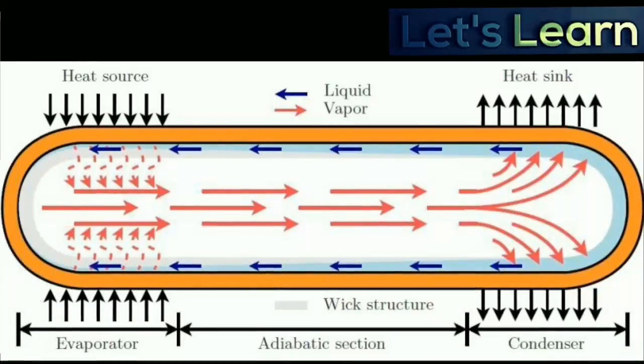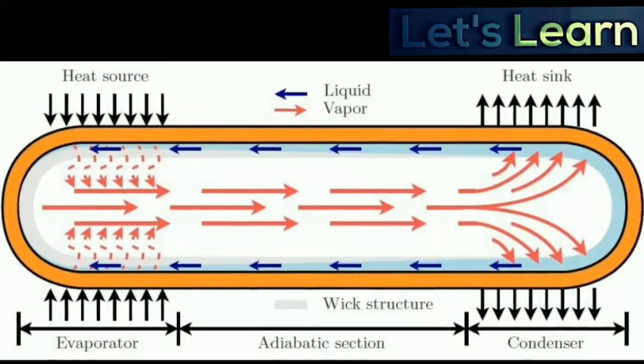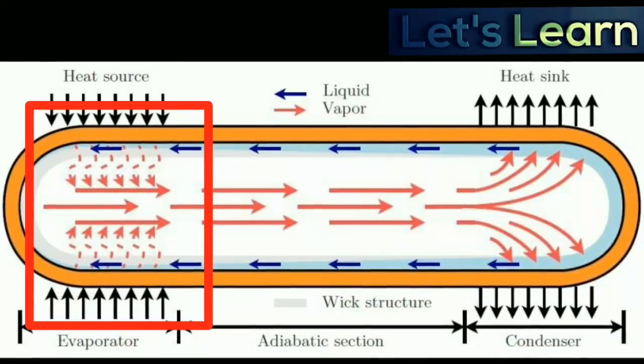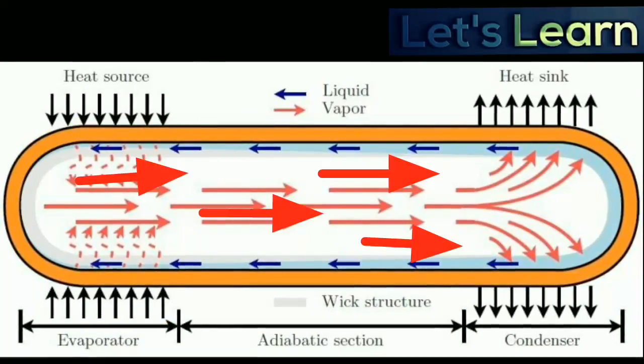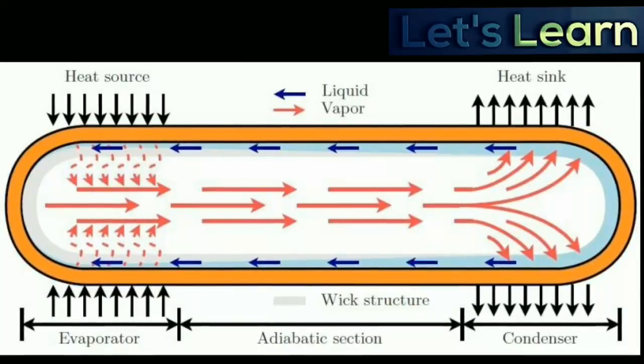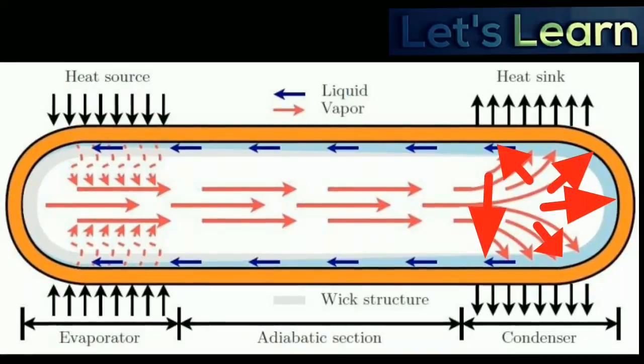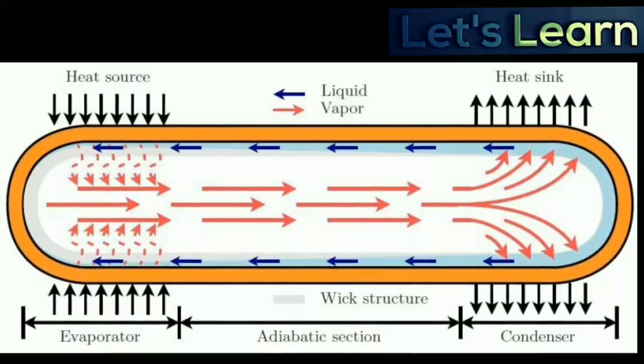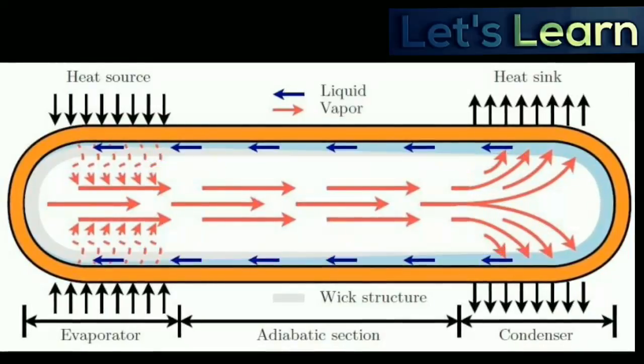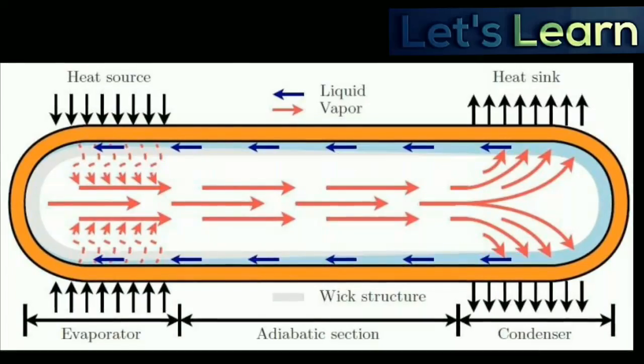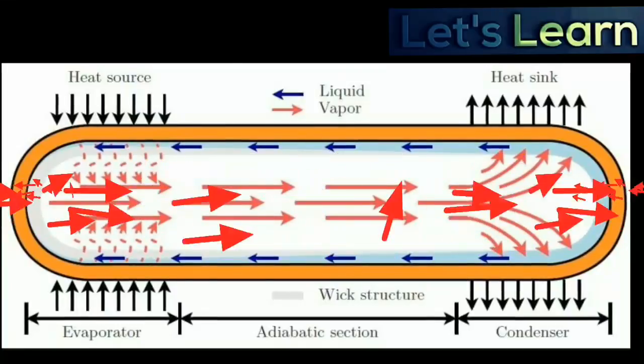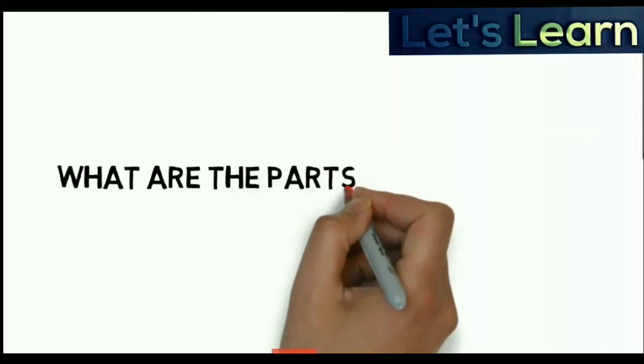Now let's see the working principle of the heat pipe. At the hot interface of the heat pipe, a liquid in contact with a thermally conductive solid surface turns into a vapor by absorbing heat from that surface. The vapor then travels along the heat pipe to the cold interface and condenses back into a liquid, releasing the latent heat. The liquid then returns to the hot interface through either capillary action, centrifugal force, or gravity, and then the cycle repeats.